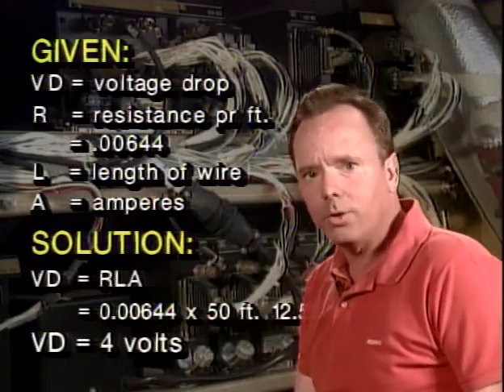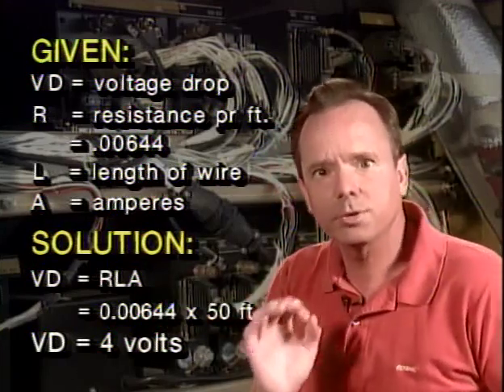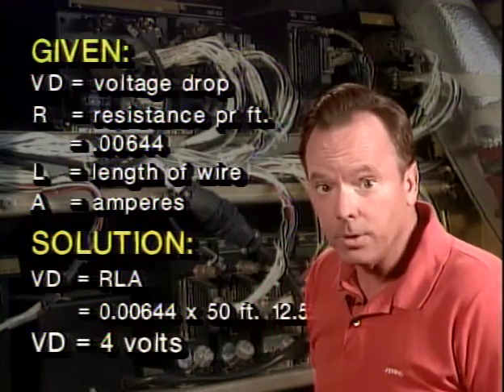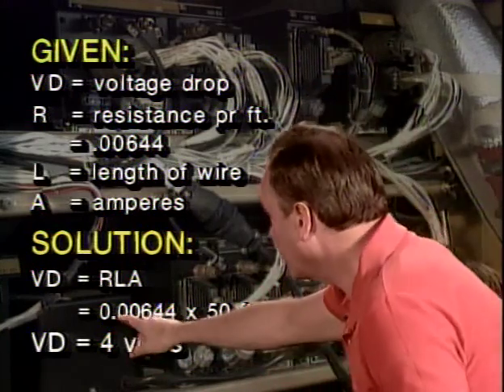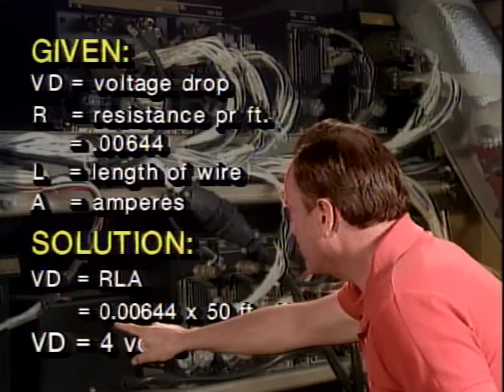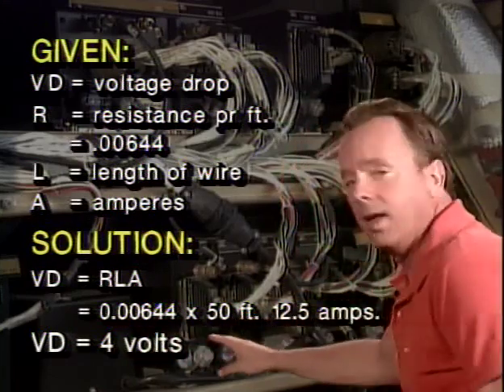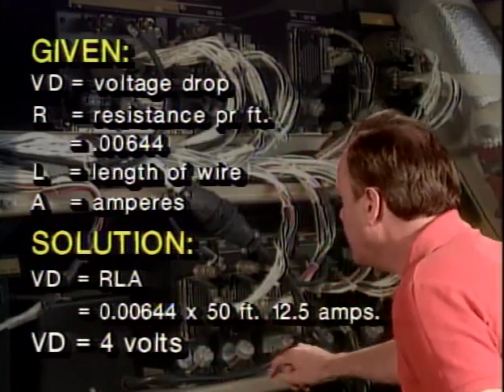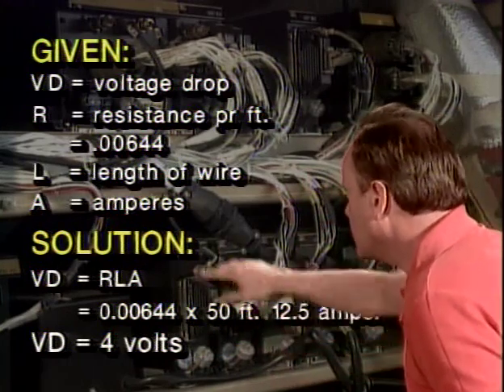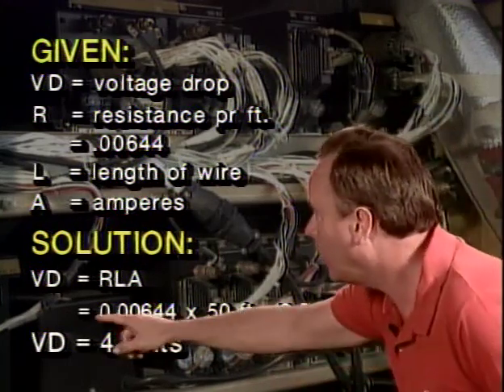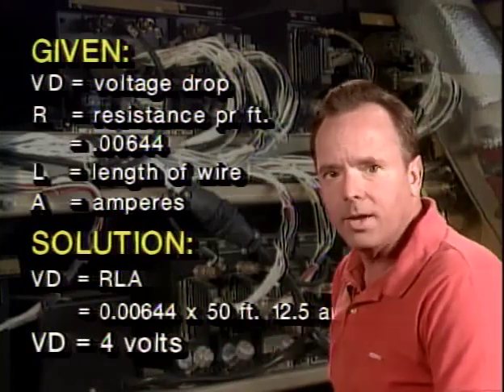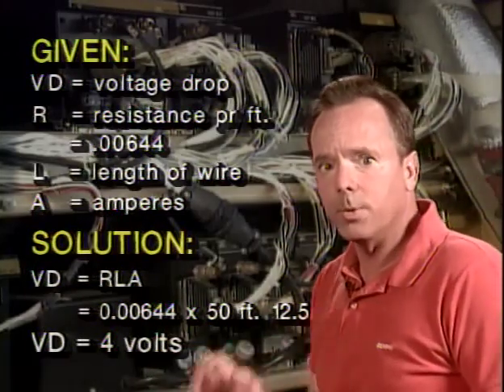So now all you have to do is plug in the numbers with your electronic calculator, and you and I have solved the problem. So let's take a look at it. First of all, the resistance is 0.00644, and the distance is 50 feet, and the amperes is 12.5 amps. You multiply all that together, and your voltage drop is 4 volts. And that's all there is to it. And they will give you, believe it or not, all of this information on the test.